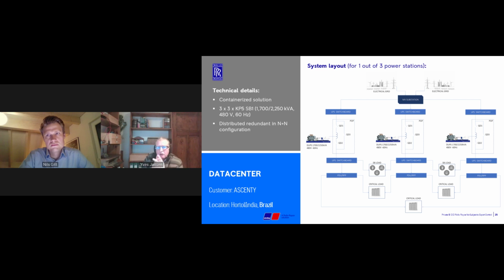The key feature of a distributed redundant topology is the distribution of the dual-corded critical load, the IT racks that are dual corded, through independent and separated dynamic UPS units. It allows achieving N plus N redundancy with UPS units loaded at a higher level than 50% of their nominal rating.